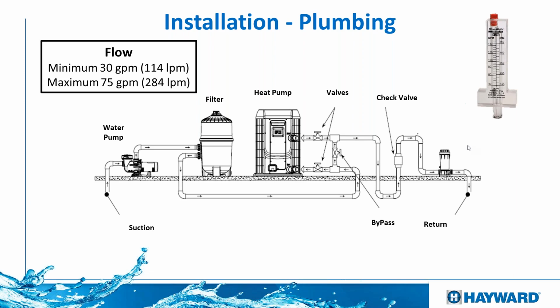Also, I want to make a comment here that if we have a chlorinator, as you can see here at the end, first of all, the chlorinator, either a salt chlorinator or a tablet feeder, needs to be at the end of the sequence. That needs to be installed all the way to the end, because we don't want pure chlorine flowing through our equipment. It will damage our pump mechanical seal. It will damage our heat exchanger, since it's made out of metal. So make it the last thing, and also put a check valve between the chlorinator or the tablet feeder and the heaters. So at night, when the pump shuts off, the chlorine does not back up into the heat exchanger, accumulate, and then cause damage overnight. So put a check valve, definitely recommend it.